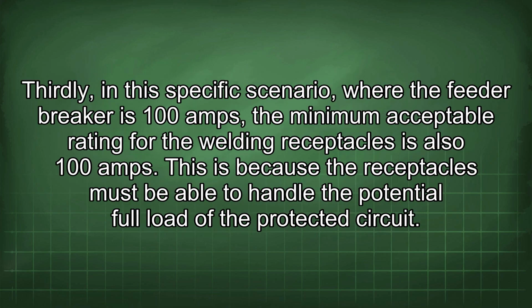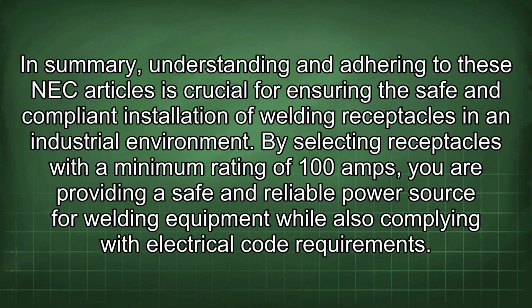Thirdly, in this specific scenario, where the feeder breaker is 100 amps, the minimum acceptable rating for the welding receptacles is also 100 amps. This is because the receptacles must be able to handle the potential full load of the protected circuit. In summary, understanding and adhering to these NEC articles is crucial for ensuring the safe and compliant installation of welding receptacles in an industrial environment. By selecting receptacles with a minimum rating of 100 amps, you are providing a safe and reliable power source for welding equipment while also complying with electrical code requirements.